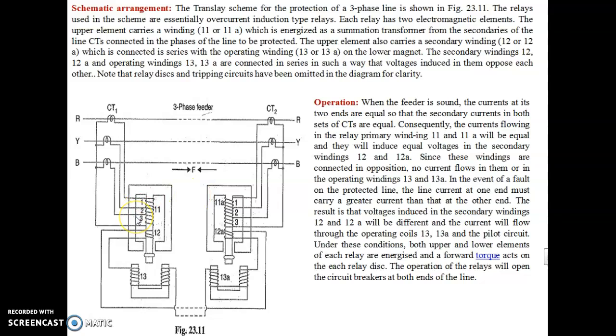Is it clear? In the Translay relay, at the start, under the normal condition or external fault condition, no current circulates through the relay coil. Why? Because the lower magnet of the relay doesn't carry any current. Okay, no torque is produced, no force is produced at the lower side. Hence no operating torque is created in these two. Hence there is no operation of the relay. If a fault occurs here, an internal fault, the primary current produces secondary current, and the secondary is directly connected to the operating coil. The operating coil also energizes, and it produces fluxes. The upper flux and lower flux interact to produce the torque. The operating torque is obviously greater than the restraining torque. Hence the relay starts operating and sends a signal to the circuit breaker. This is the overall concept of the Translay relay.